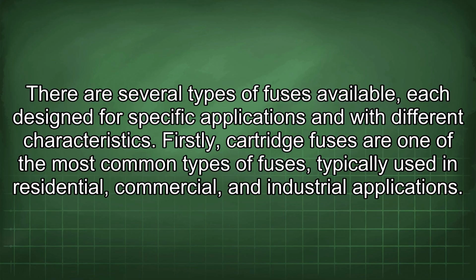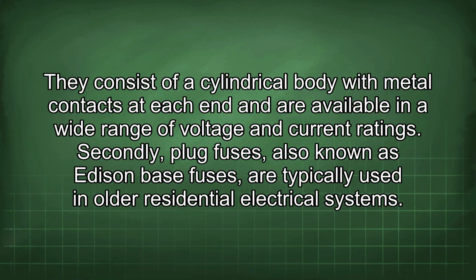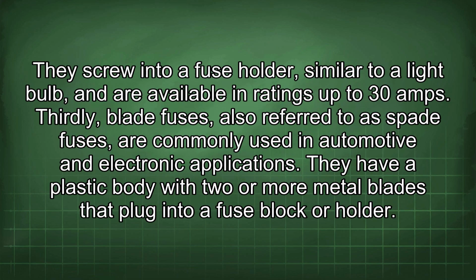Firstly, cartridge fuses are one of the most common types of fuses typically used in residential, commercial, and industrial applications. They consist of a cylindrical body with metal contacts at each end and are available in a wide range of voltage and current ratings. Secondly, plug fuses, also known as Edison base fuses, are typically used in older residential electrical systems. They screw into a fuse holder similar to a light bulb and are available in ratings up to 30 amps.